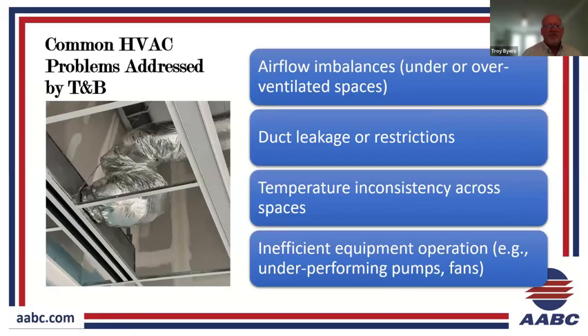All right, so some of our common problems that are addressed in existing buildings, and feel free to add some of your own experiences. Airflow imbalances. If we're out of balance for ventilated spaces, might have duct leakage. We talked about restrictions. Here's a picture of a restriction in a flex duct. We just have too much flex duct, or maybe the hard duct is extended too far, and we're trying to bring that flex back in front of that slot diffuser to connect to it. And now we just got this Z-shape restriction there. That system has to overcome that restriction to get the airflow out of the grill.